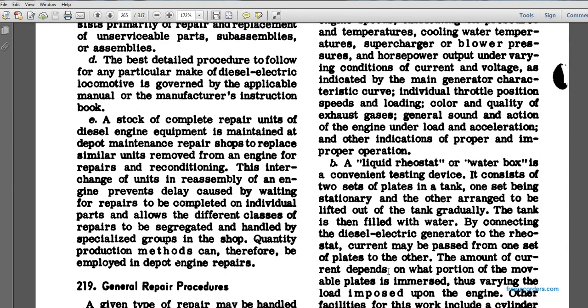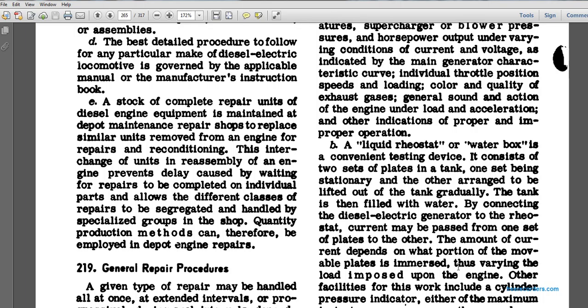A liquid rheostat or water box is a convenient testing device that consists of two sets of plates in a tank. One set is stationary, the other arranged to be lifted out of the tank gradually. The tank is filled with water. By connecting the diesel-electric generator to the rheostat, current may be passed from one set of plates to the other. The amount of current depends on what portion of the movable plates is immersed, thus varying the load imposed upon the engine.